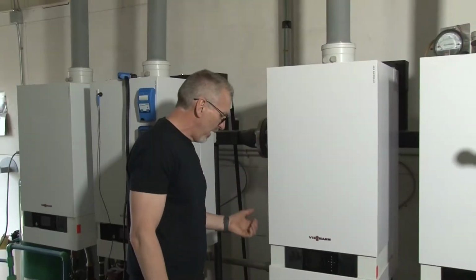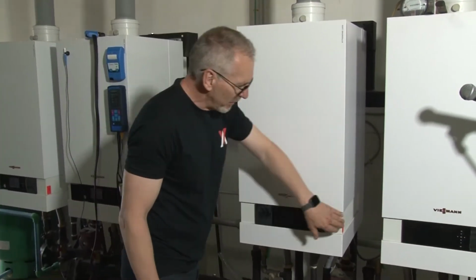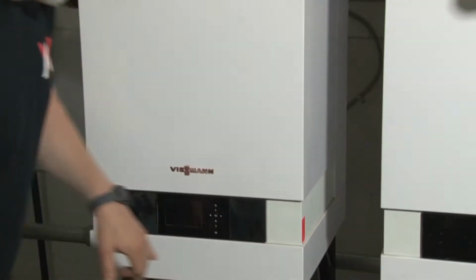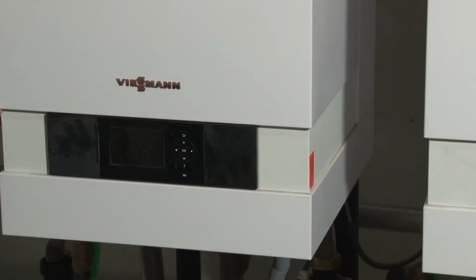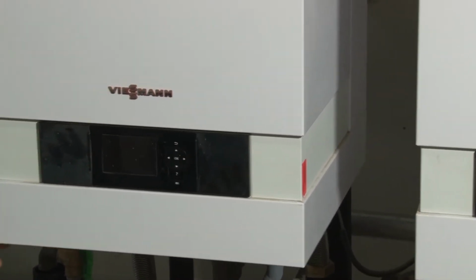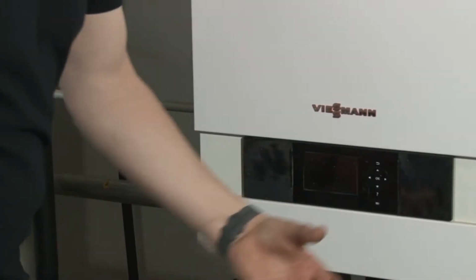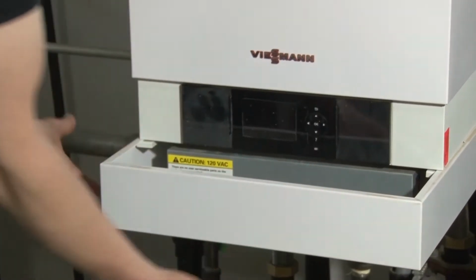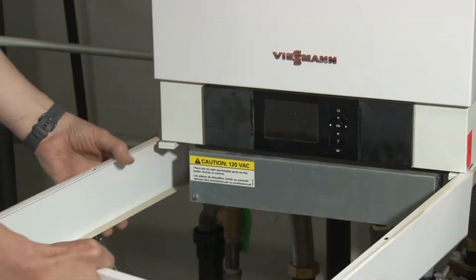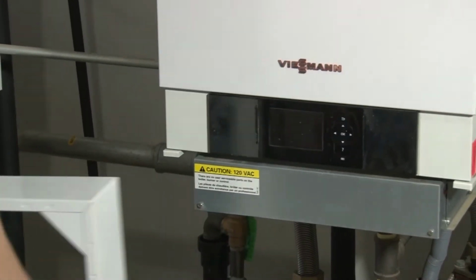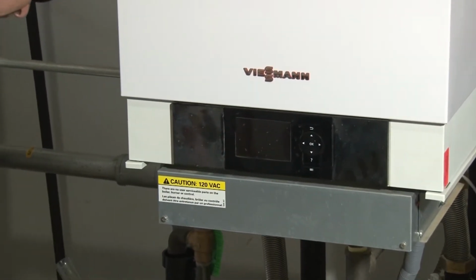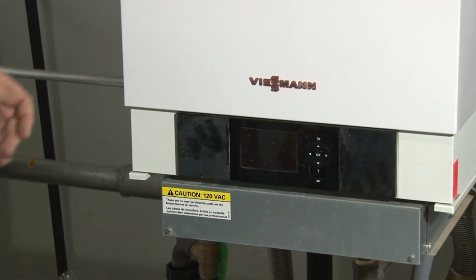So first thing, on the side of the boilers, there's these little red stickers, and they're identifying that holding this door on is a screw. The little Phillips head screw is on the bottom here. You would have to remove the little skirt, I call it, underneath the boiler here. So you can take the skirt off here, a little skirting. Put that aside there for a second.